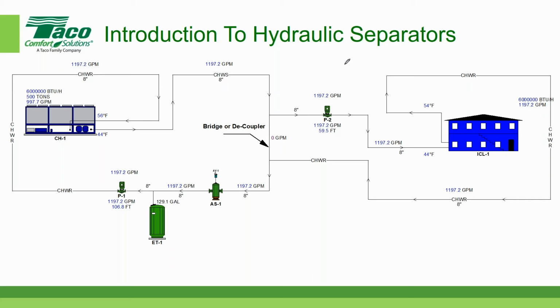And yes, maybe you want to clarify that some people will refer to it as a low loss header. You can think of this pipe here as three sections of pipe: section 1, section 2, and section 3. You can think of this as a header, and the pressure drop across that header is negligible. So sometimes we use the term low loss, which means low pressure loss or no pressure change header. That's another term used for the bridge, decoupler, hydraulic separator, low loss header, and so on. There are multiple names for the same thing, the same phenomenon.